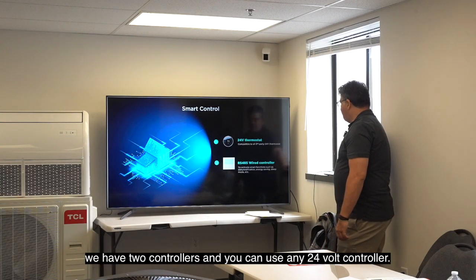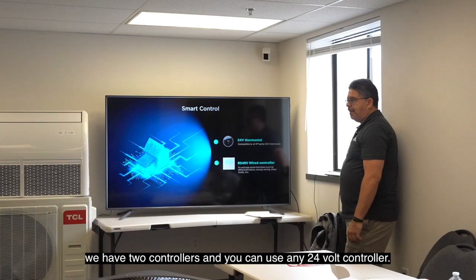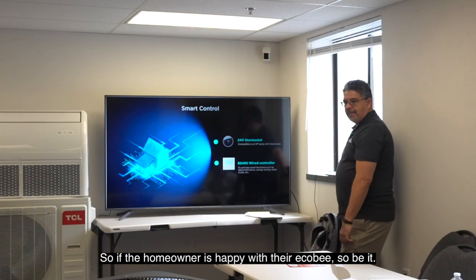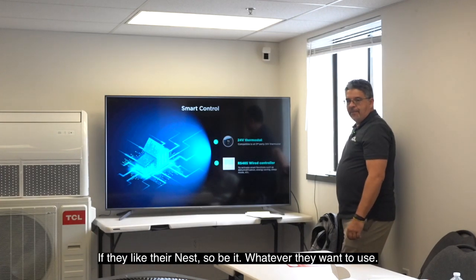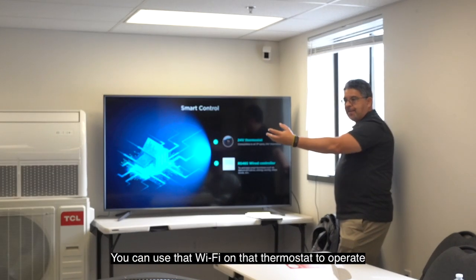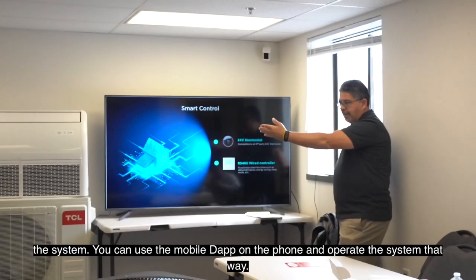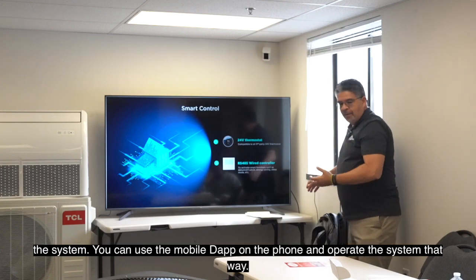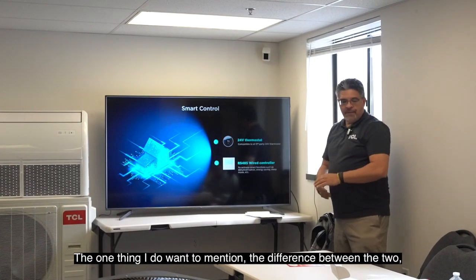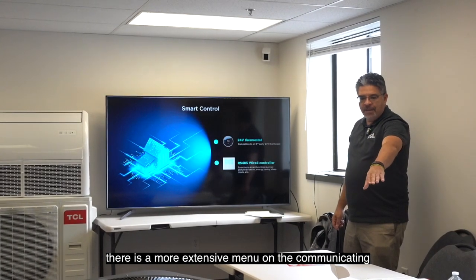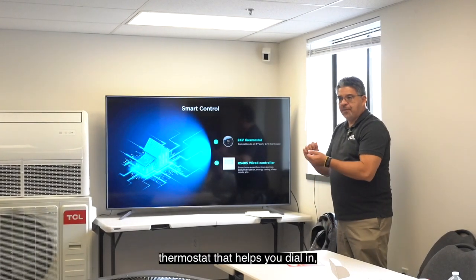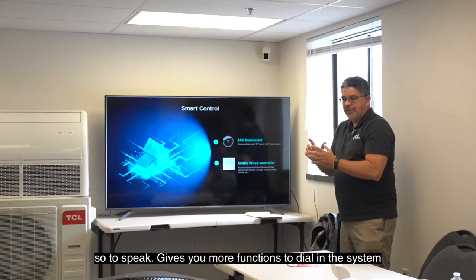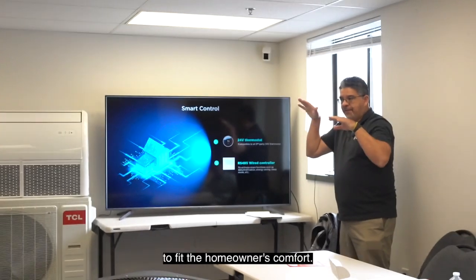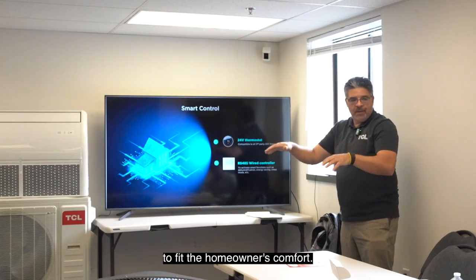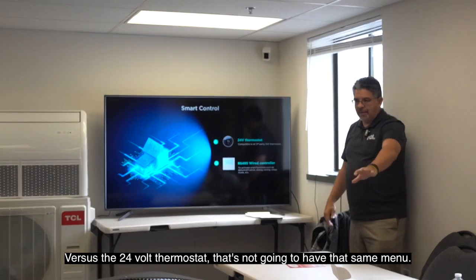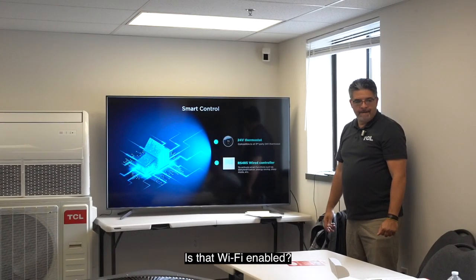Anyway, we have two controllers, and you can use any 24-volt controller. So if the homeowner is happy with their Ecobee, so be it. If they like their Nest, so be it. Whatever they want to use. And you can use that Wi-Fi on that thermostat to operate and download the app on the phone and operate the system that way. The one thing I do want to mention, the difference between the two. There is a more extensive menu on the communicating thermostat that helps you dial in, so to speak, gives you more functions to dial in the system to fit the homeowner's comfort, versus the 24-volt thermostat that's not going to have that same menu. Is that Wi-Fi enabled?